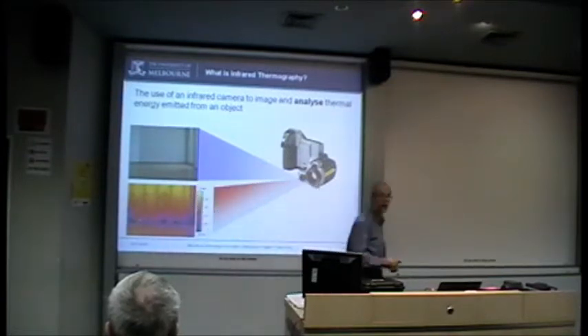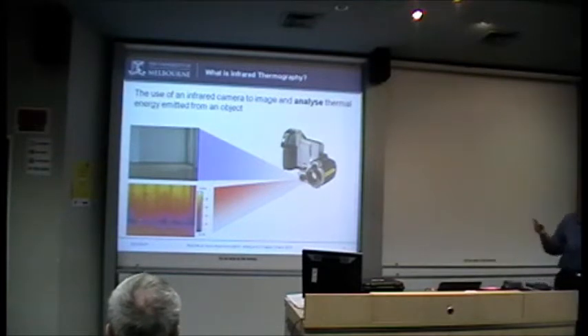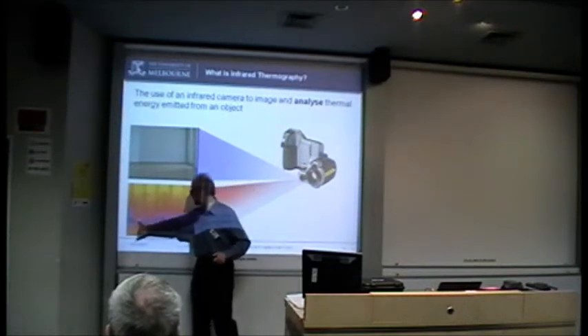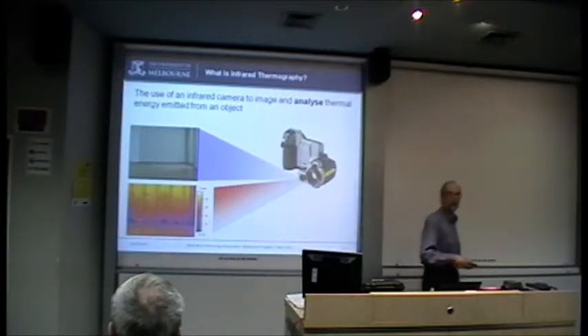Because it is a hotter spot, isn't it? It is hot. So that's not wrong. Warm. It's warmer, but it's hot. But a matter of interpretation, is it because we've got a leakage there or something else? In this case, I'm fairly sure it's not a leakage because we know that what's behind is cold. So if that's letting a leak, I expect it to be darker around that, not bright. Might be a poor connection out of that.